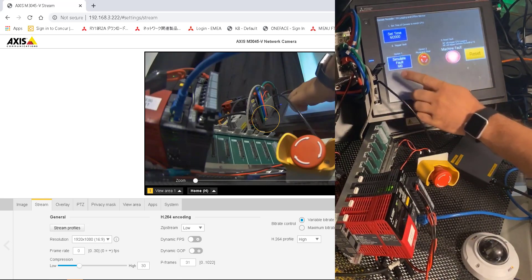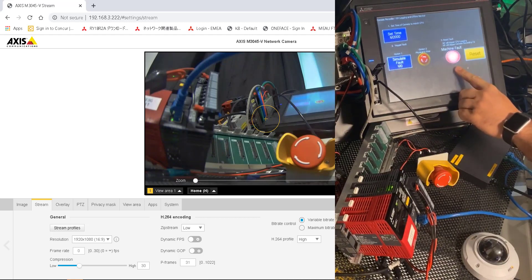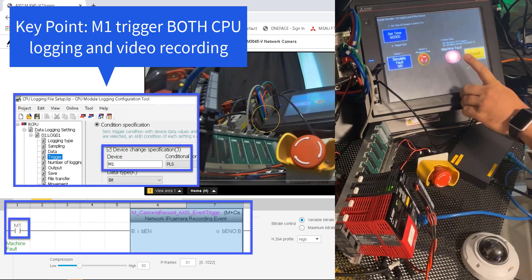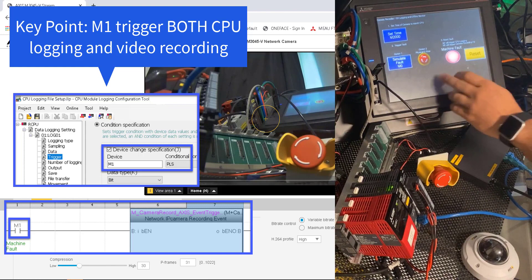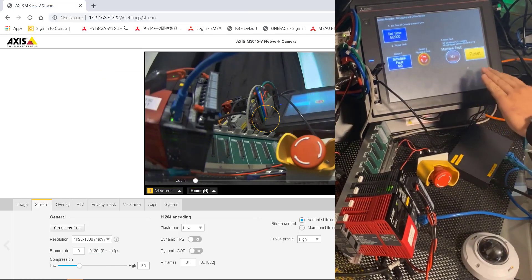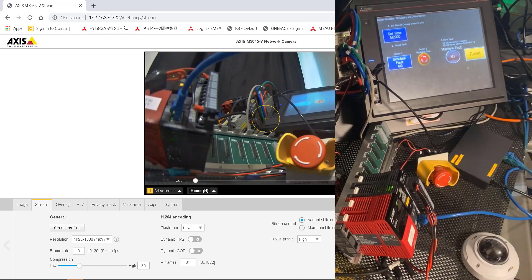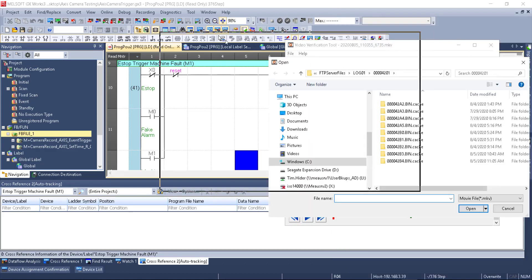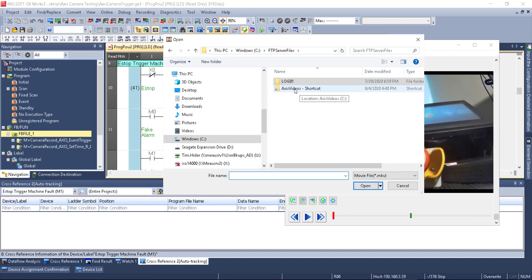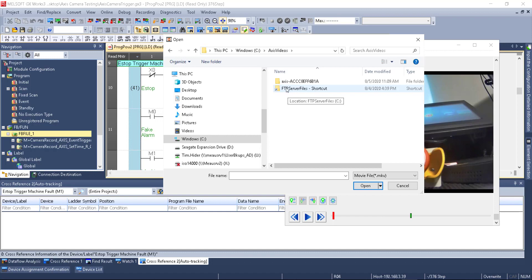Now let's trigger a simulated fault using the HMI. We press the button, M1 turns on — M1 is both our CPU logging trigger and our camera file recording trigger. That should have given us a file from the camera as well as a logging file from the PLC. We take the fault off, clear the fault, and go back to see what actually happened. First, we'll bring up the video verification tool and open our video file from the Axis Videos folder.